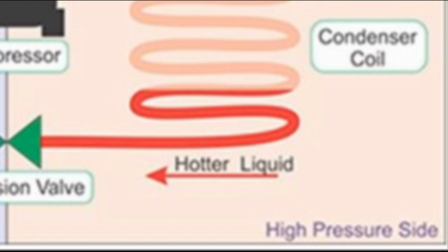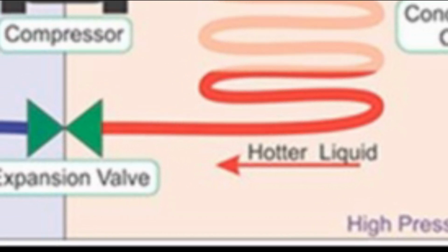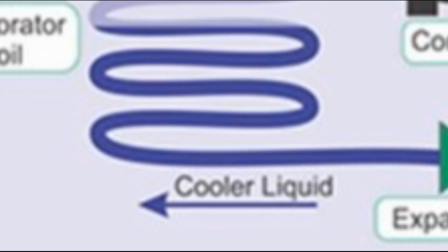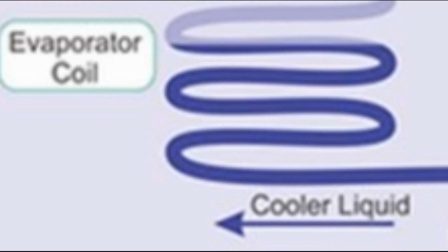The liquid refrigerant continues through the coil until it reaches the expansion valve. This is typically either an electronically or mechanical pressure adjusted valve that restricts the liquid and meters it into the low pressure evaporator in a controlled manner. This liquid entering the evaporator is in a state of a saturated fluid. Fluid is technically not always a liquid, and gas is also fluid.